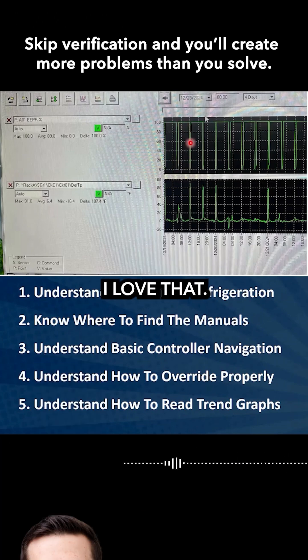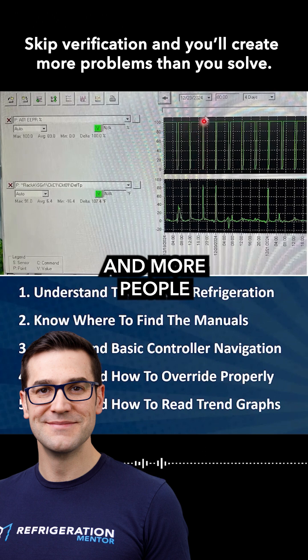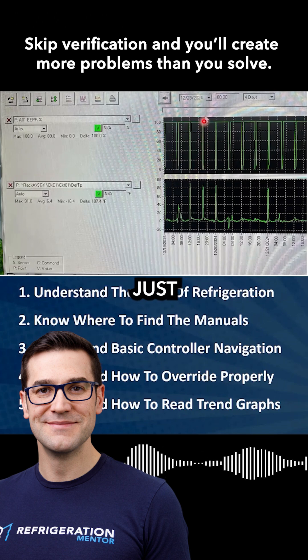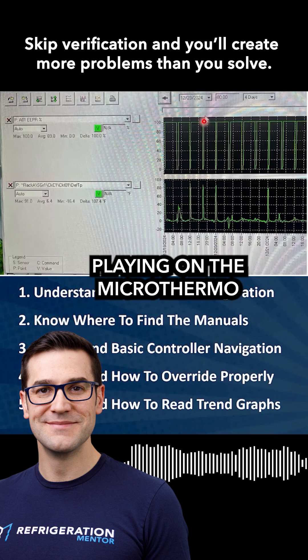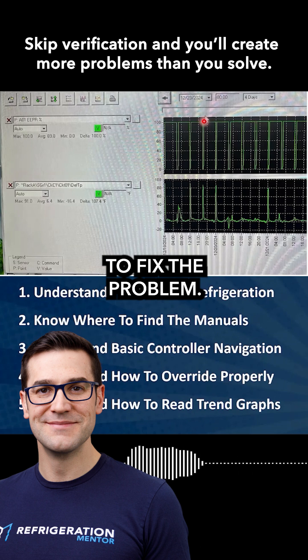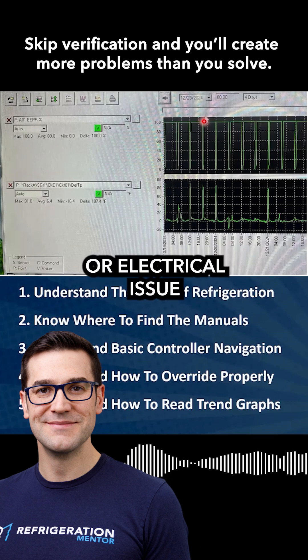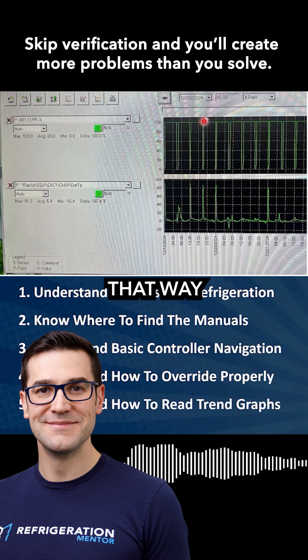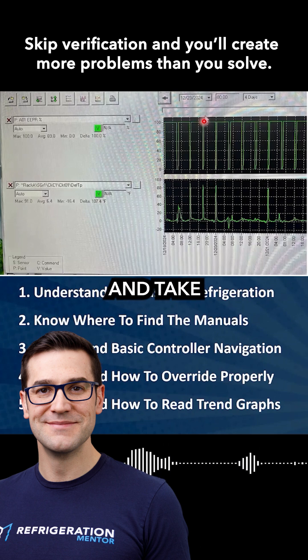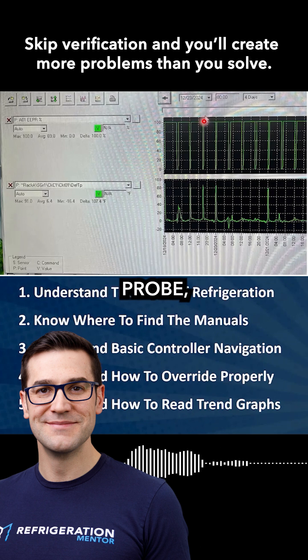I love that, because I've been hearing and seeing more and more people trying to troubleshoot just from the controller. They're up playing on the MicroThermo, the E2, Danfoss — and they're trying to fix a problem that is more of a mechanical or electrical issue that you can't fix that way. You have to go out and take a temperature probe that reads accurately.